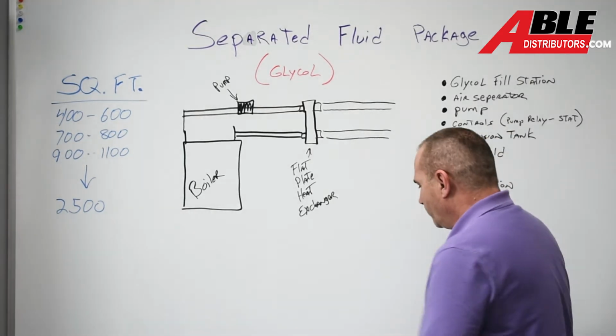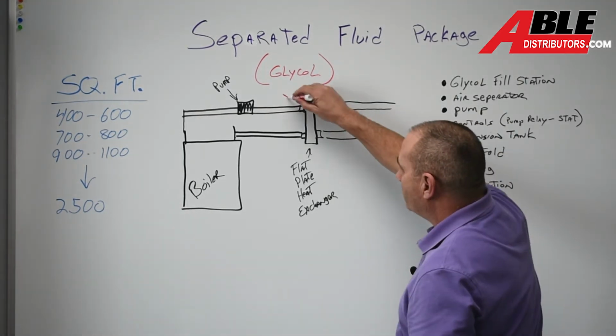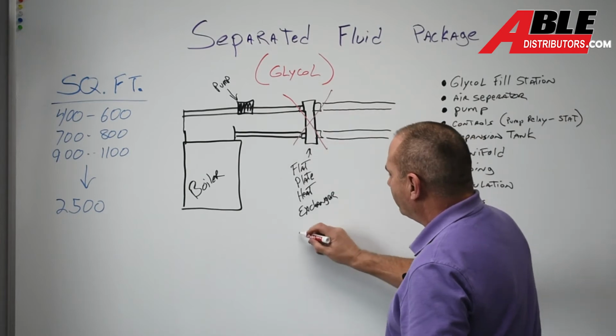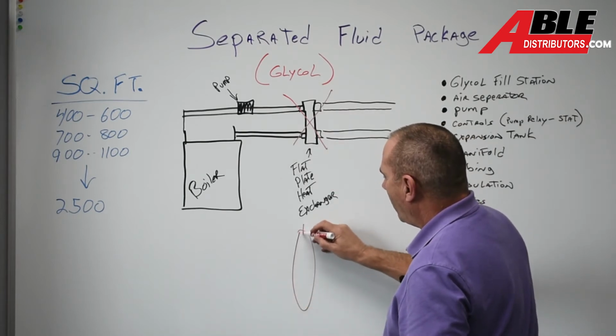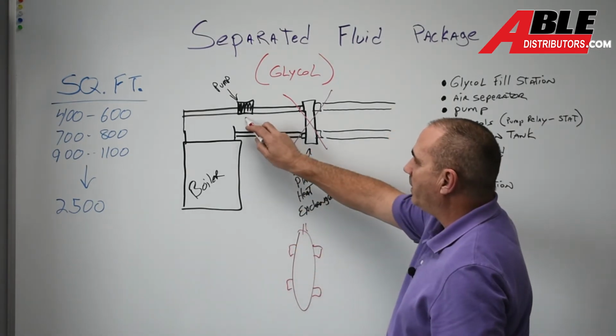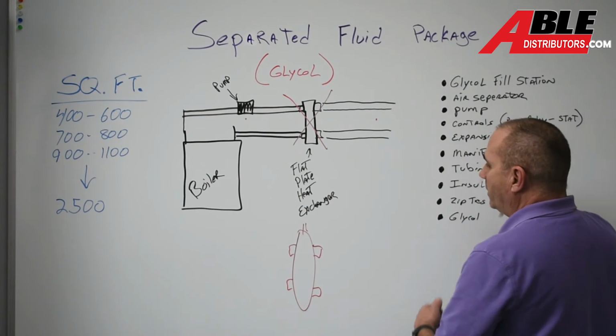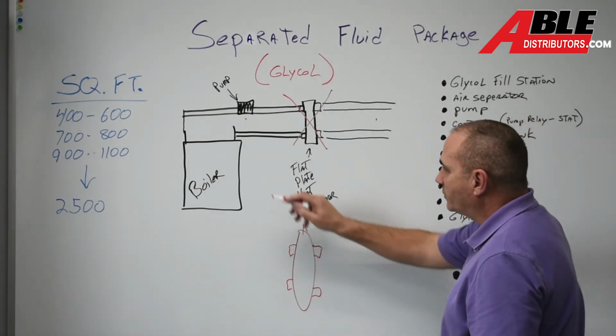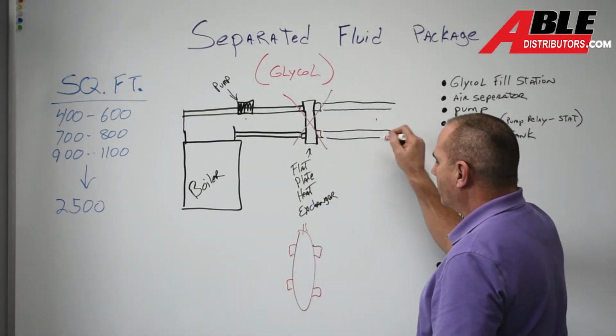In that situation, what I would do is eliminate that and put in a hydro air separator. It would allow you to still keep this pump here, still have all the parts here, but now you've got a nice primary loop, secondary loop.